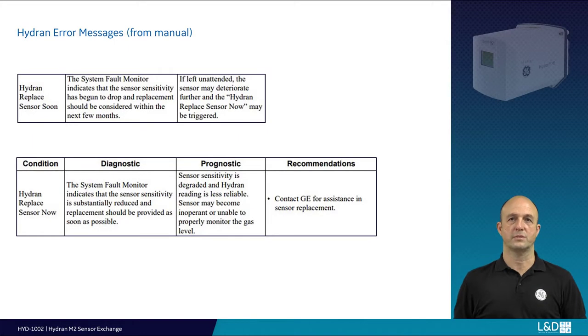When would you replace your sensor? Normally, you will receive either of these service condition alarms: 'Replace sensor soon' — we would recommend a sensor replacement within 90 days — or 'Replace sensor now', for which we would recommend that you replace the sensor immediately for continued transformer monitoring.